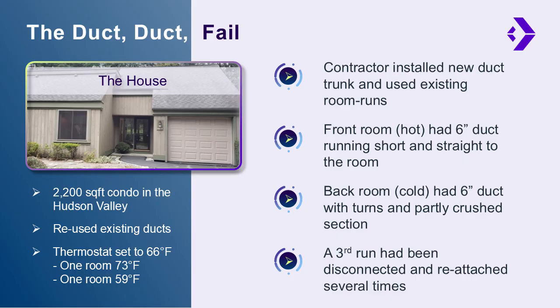A little digging found the front room, which was hot, had a 6-inch duct running short and straight to that room. The back room, which was cold, had a 6-inch duct, but it meandered with multiple turns and had a partly crushed section going over a joist. To make matters worse, a third duct run continued to get disconnected and had been reattached several times already. Chronic issues undercut any other improvements being made. These issues highlight the importance of properly evaluating and addressing ductwork prior to installation. Uneven duct runs, crushed sections, and poor connections can lead to significant comfort issues and inefficiencies in the system.